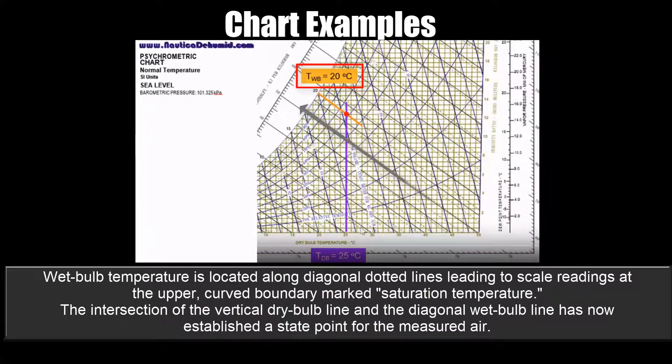Wet bulb temperature is located along diagonal dotted lines leading to scale readings at the upper curved boundary marked saturation temperature. The intersection of the vertical dry bulb line and the diagonal wet bulb line has now established a state point for the measured air.